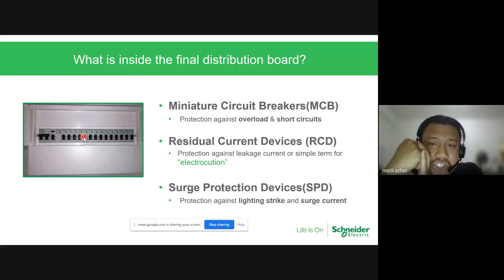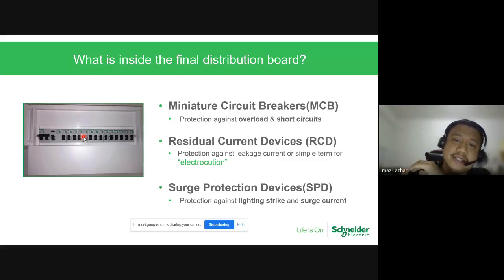Simple. You have a miniature circuit breaker. If you go to study, you will see at the substation or distribution from the TNB, you have ACB, air circuit breaker, vacuum circuit breaker, whatever design of circuit breaker. So this is the miniature type of circuit breaker, which provides protection against overload and short circuit. You will have a residual current device, protection against leakage current, or in simple terms, electrocution. And then you will have an SPD, protection against lightning strike and surge current. I will go through these one by one.